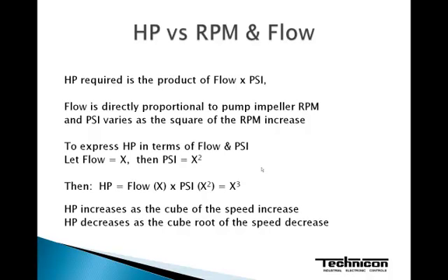So we would be fair in saying that as we increase the RPM or speed, the load or horsepower increases by the cube of that increase. Conversely, if we reduce the flow or RPM of our system, then the horsepower or load decreases as the cubed root of that speed decrease.